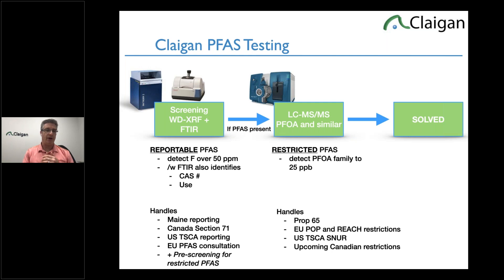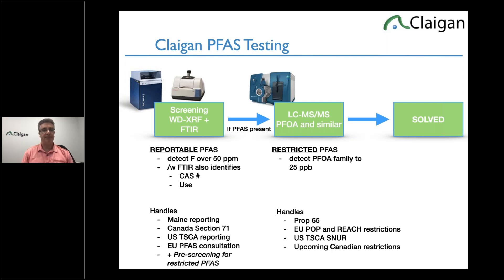However, EDXRF has trouble with lighter elements higher up the periodic table. One reason is oxygen error — the fluorine signal gets attenuated by air: oxygen, argon, and nitrogen all take away a lot of the signal. So you need a WDXRF, which is much more powerful and operates under vacuum, allowing it to test fluorine directly. It's even better in a lot of ways than combustion bomb analysis because we can distinguish coatings from internal materials — we can see fluorocoating really well.